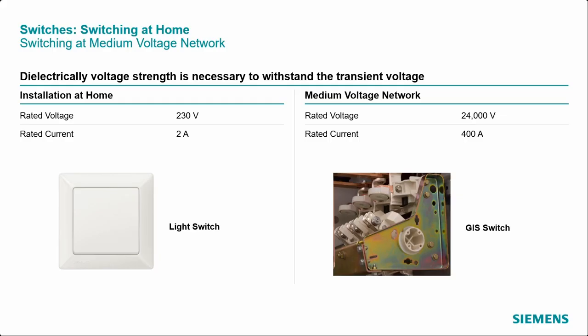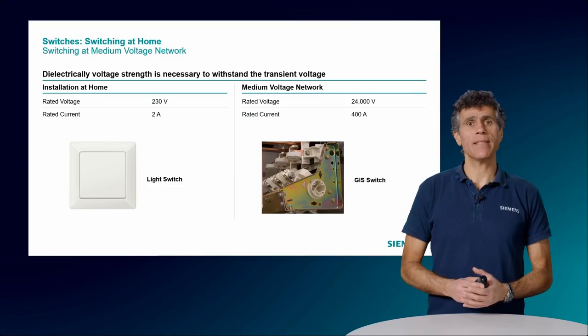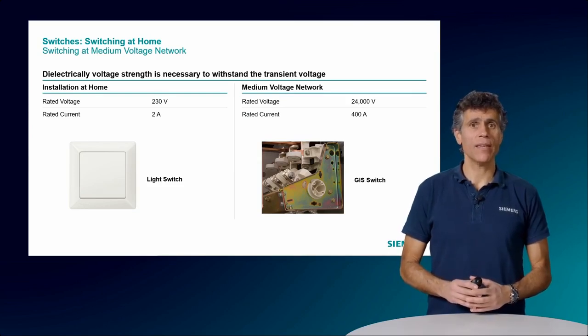Another type of device is the switch. The switch can make or break a circuit while a defined operating current is being passed through it. Essentially, it is designed to interrupt the current flow in a system, but it is not intended to interrupt short circuit currents like a circuit breaker does. It can switch into a short circuit, but it can't open it. In that regard, it is similar to a contactor, but it's a much simpler device. It can deal with higher currents than a contactor, but it cannot switch nearly as often as a contactor.